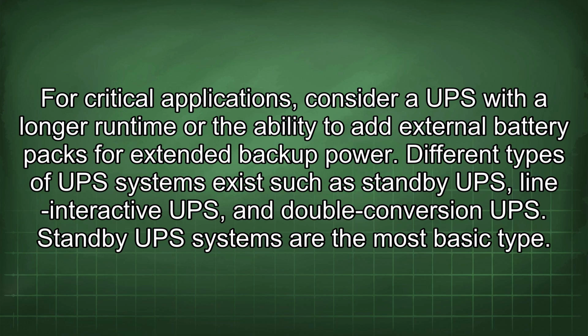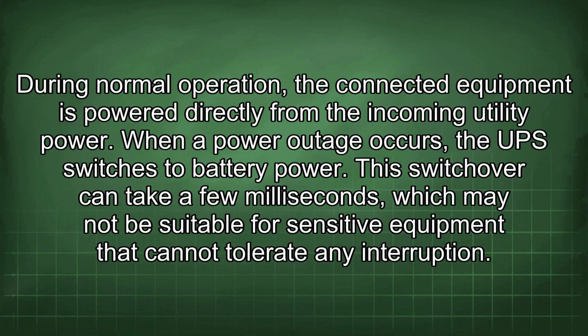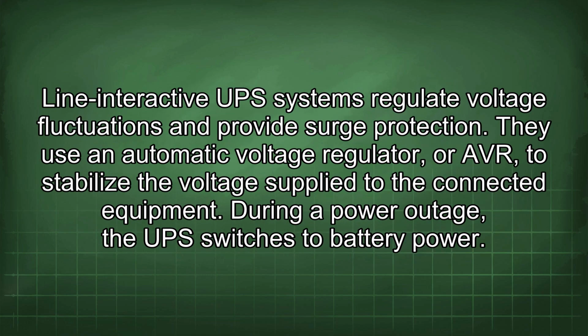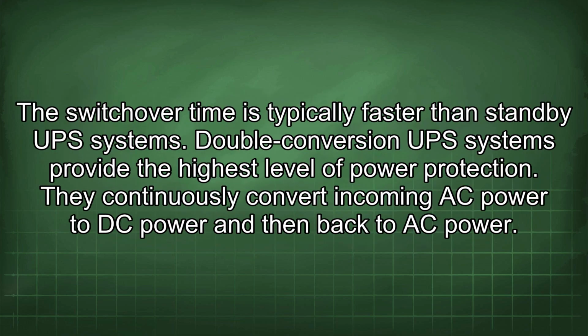Standby UPS systems are the most basic type. During normal operation, the connected equipment is powered directly from the incoming utility power. When a power outage occurs, the UPS switches to battery power. This switchover can take a few milliseconds, which may not be suitable for sensitive equipment that cannot tolerate any interruption. Line interactive UPS systems regulate voltage fluctuations and provide surge protection. They use an automatic voltage regulator, or AVR, to stabilize the voltage supplied to the connected equipment. During a power outage, the UPS switches to battery power. The switchover time is typically faster than standby UPS systems.